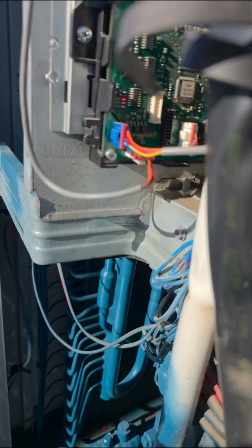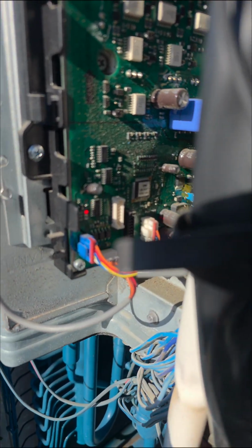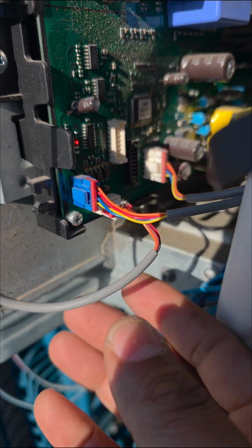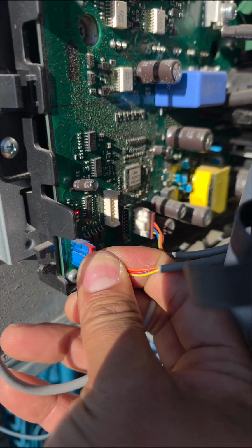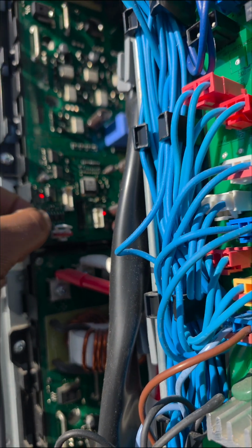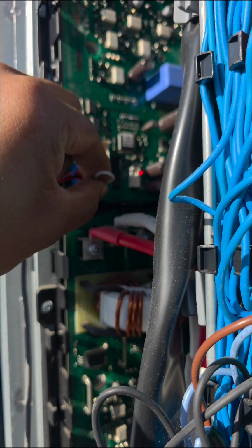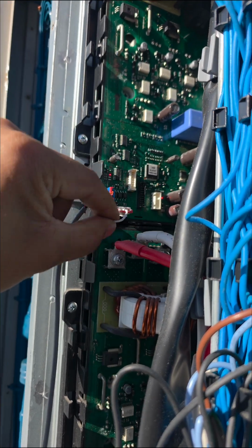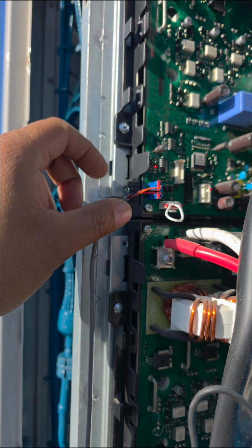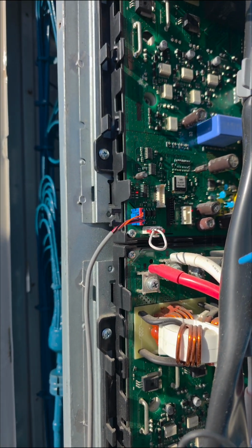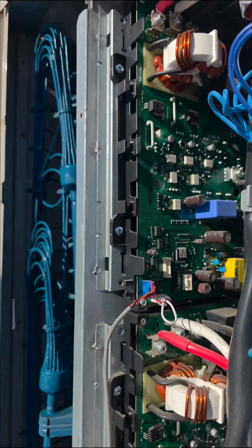And that is the main communication between your fan board and your inverter board. So that was just something very interesting to note. At the moment it's fine, but this one definitely gave us an issue as well. And this essentially just loops the comms, the 5-volt comms line, back. This is the end of the communication chain on all our outdoor PC boards.